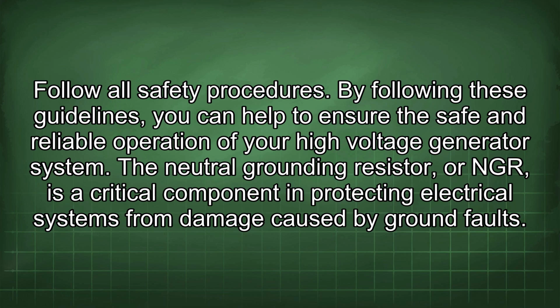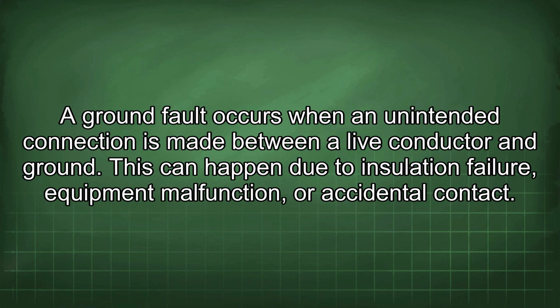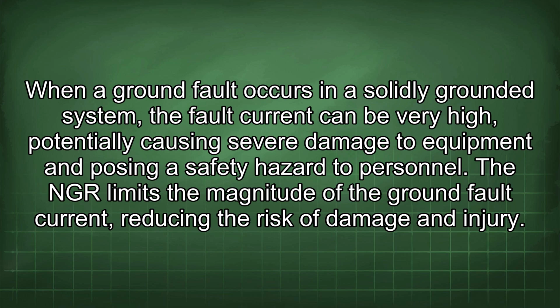The neutral grounding resistor, or NGR, is a critical component in protecting electrical systems from damage caused by ground faults. A ground fault occurs when an unintended connection is made between a live conductor and ground. This can happen due to insulation failure, equipment malfunction, or accidental contact. When a ground fault occurs in a solidly grounded system, the fault current can be very high, potentially causing severe damage to equipment and posing a safety hazard to personnel. The NGR limits the magnitude of the ground fault current, reducing the risk of damage and injury.